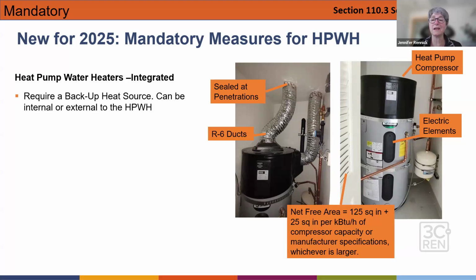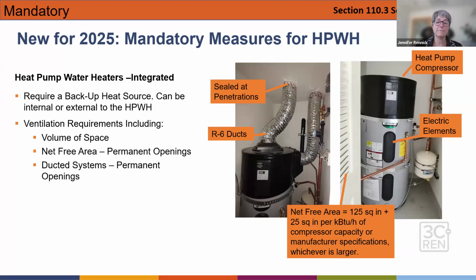So that could be just the electric elements that are already in the tank. Then there's going to be ventilation requirements, and that is going to include how much volume of space is available for the heat pump compressor that sits on top of the tank. And then there's going to be requirements for a ducted system, and if they have permanent openings, but also if you don't have a ducted system, there's requirements for the net free area in, say, a louvered door.